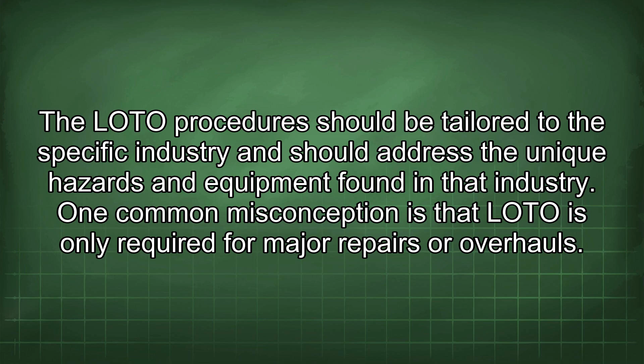One common misconception is that LOTO is only required for major repairs or overhauls. In reality, LOTO is required for any activity that involves placing any part of an employee's body into a zone of danger near energized equipment. This includes clearing jams, making adjustments, or performing routine maintenance. The key is to assess the risks and implement LOTO procedures whenever there is potential for injury from unexpected energization or startup of equipment.